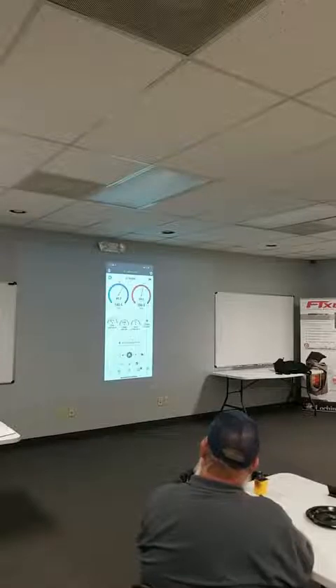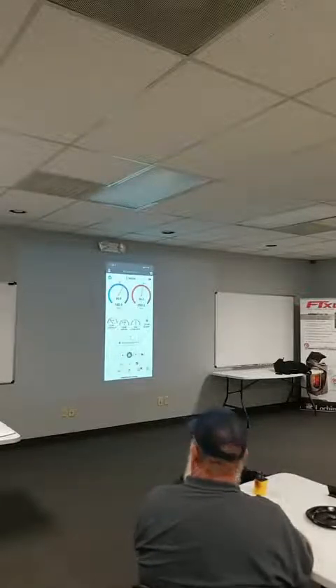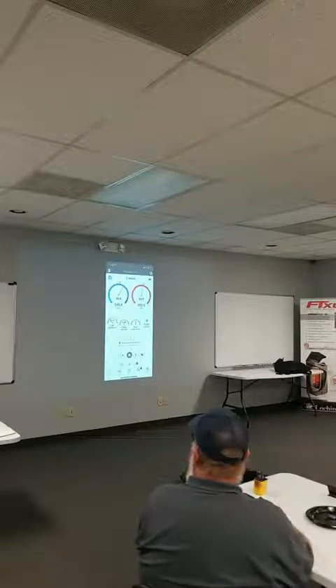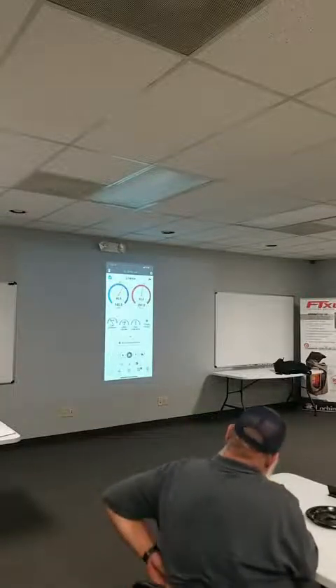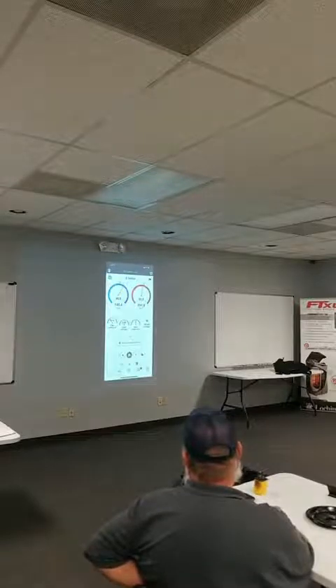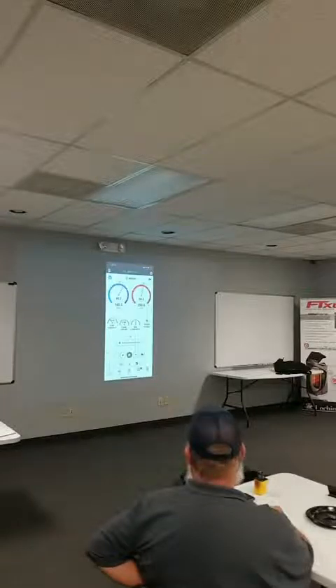You can have a split system. Let's say you have 4 compressors, but you have fixed airflow. So with 1 compressor on, you might get 5 degrees of split. Turn 2 on, you get 10 degrees. Turn 3 on, you get 15 degrees. 4, you get 20 degrees of split. And Measurequick will also recalculate what the target temperature split should be for each compressor circuit, and then with all 4 running. Where do you program that in?